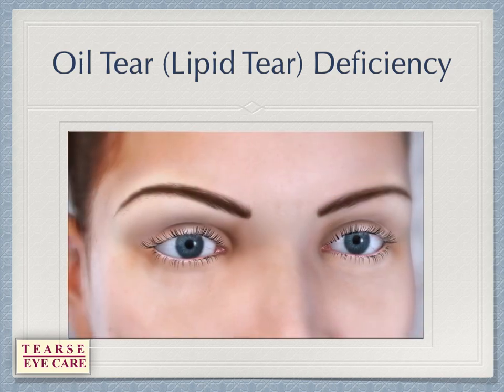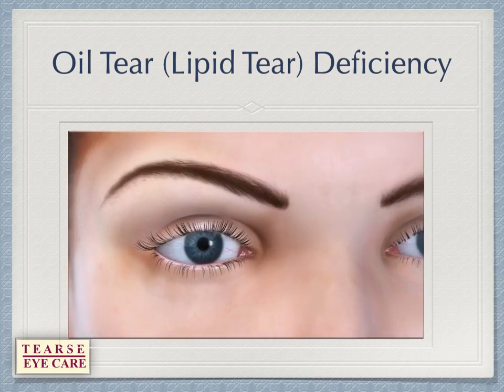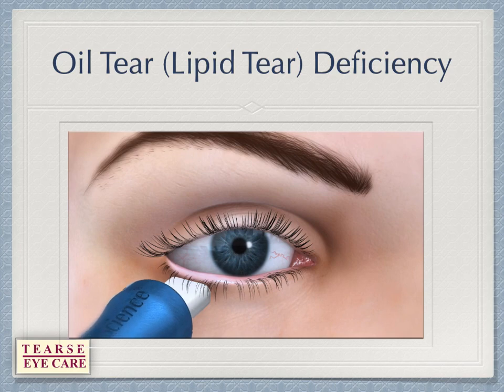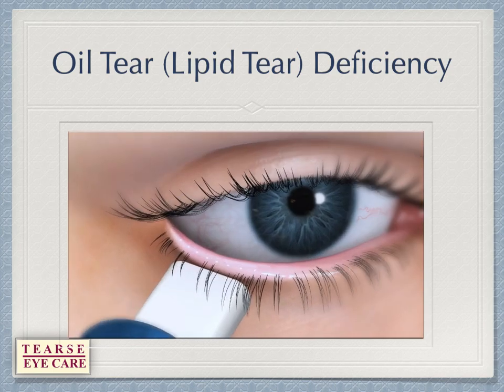Doctors now have the ability to assess meibomian gland dysfunction with a meibomian gland evaluator, or MGE. The MGE exerts pressure consistent with a deliberate blink, allowing evaluation of gland secretions in 3 regions of the eyelid. Using the MGE, secretions for 5 glands in each region are scored on a scale of 0 to 3.